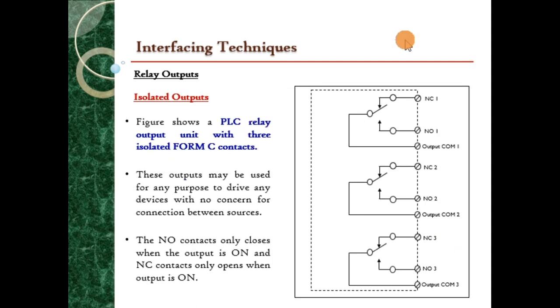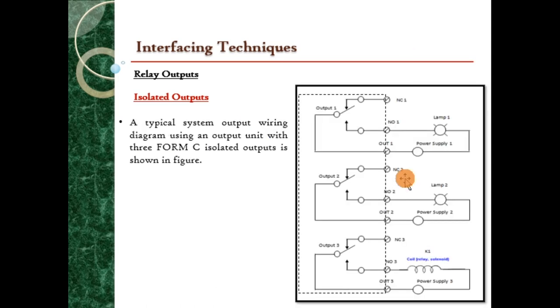Next, we have the isolated outputs. This figure shows a PLC relay output unit with three isolated Form C contacts. These outputs may be used for any purpose to drive any device with no concern for connection between sources, since all the sources are isolated. So the NO contact only closes when the output is on, and the NC contact only opens when the output is on. So there is no contact interfering between these three outputs. This is an example of the isolated outputs, so each of the output devices is not connected to the others.